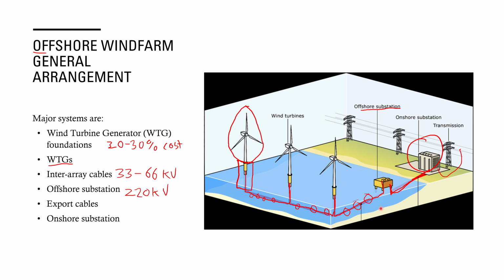There are some differences, which I'll go into more in part 2. For example, increasingly the export cable is actually a high voltage DC system, so there are converters in the offshore substation to handle that, and converters in the onshore substation. There are advantages and disadvantages to that - different array voltages, different string orientations, different switchgear, and so on.